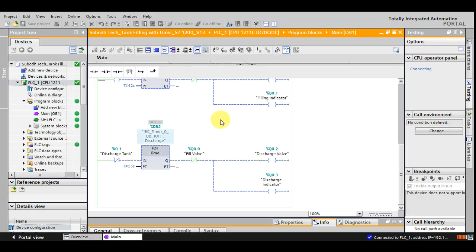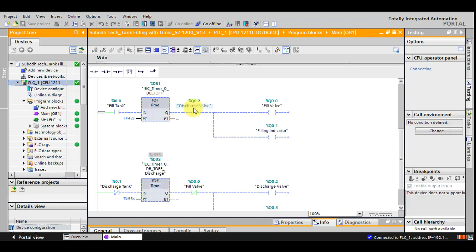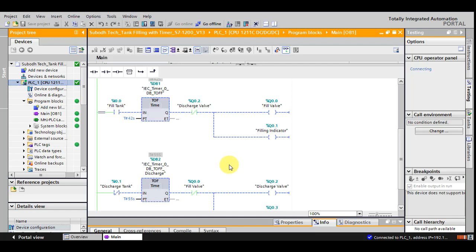And in addition to this, what I did here is I have given two interlocks also. The interlocks I have provided because, for example, if someone has pressed fill valve and then he has pressed discharge valve also, so if we are not providing this interlock, then what would happen is both the outputs would get on.